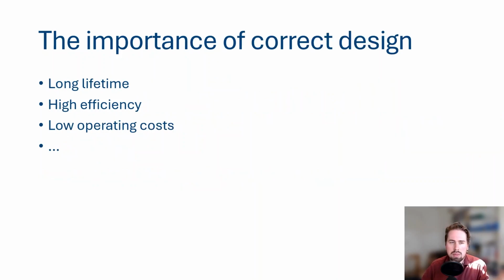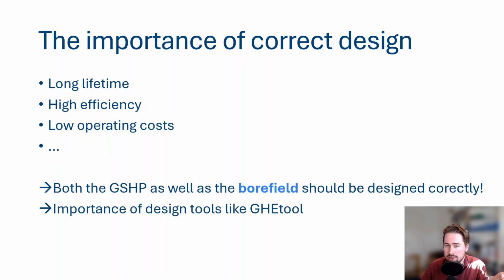Now, of course, everything we talked about, the long lifetime and the high efficiency and the low operating costs, is all contingent on the fact that your ground source heat pump should be designed correctly, but also your bore field should be designed correctly, because you can have a very good ground source heat pump. If the source, the heat source, is not well designed, if it's too small, then it can be that your system is not functioning very well. And that's actually a shame if you invest more into this ground source heat pump, that it's not functioning at its best. And that's why it's really important to use design tools like GHE Tool.